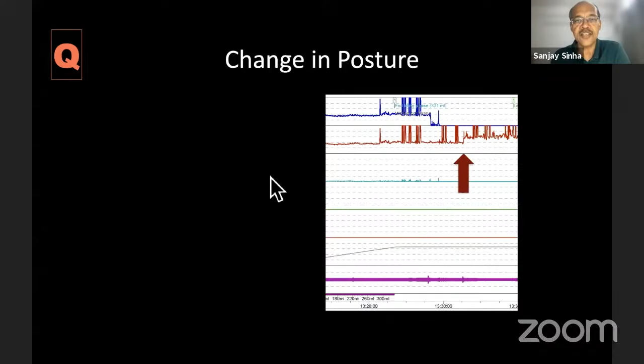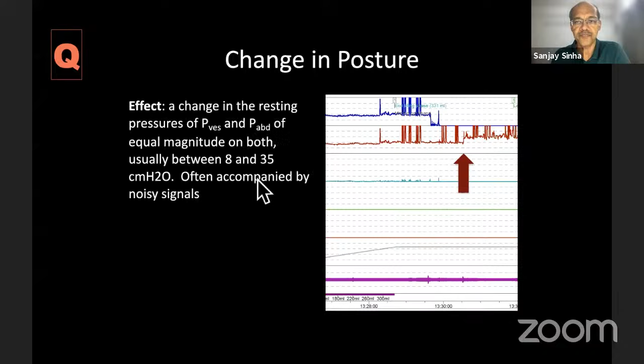Now, when the patient stands up, as you rightly mentioned, there is a change in the intra-abdominal pressure, because the abdominal pressure when you stand is higher than when you sit. But not all of this change may be because of that. Some of it can be because you have not adjusted the height of your transducer. So you must readjust the height of the transducer before you actually start recording. Otherwise, you will over-record the leak point pressures. So when the patient stands up, readjust the height of the pressure transducers back to the superior border of the pubic symphysis.